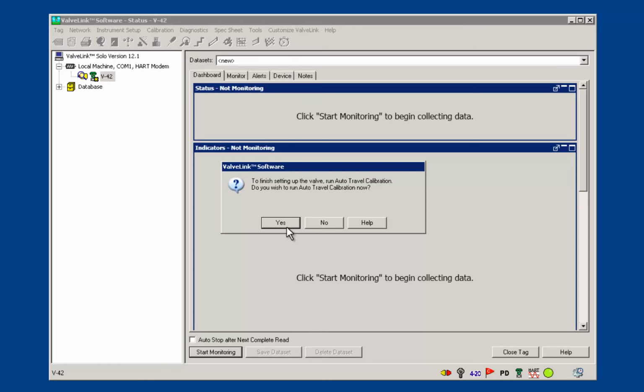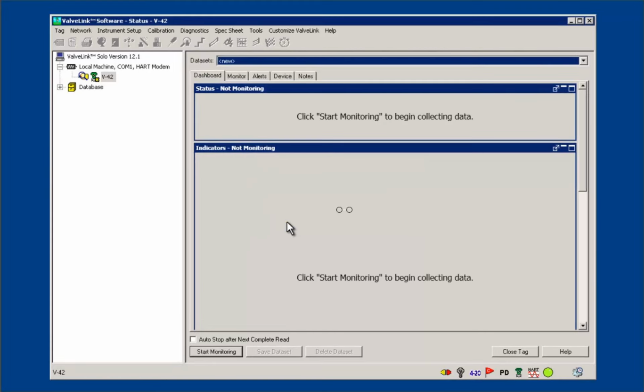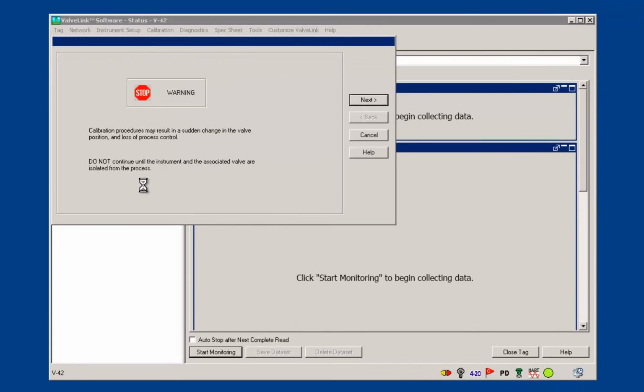You should now choose to run Auto Travel Calibration. These will cause the valve to move, so ensure the instrument and valve assembly is isolated and not exposed to any live processes, or a process upset will occur. This window offers a warning that the valve will move now. Click Next to continue. It will now calibrate.